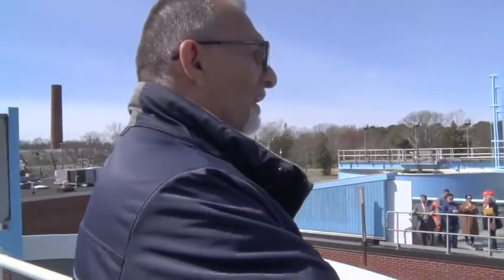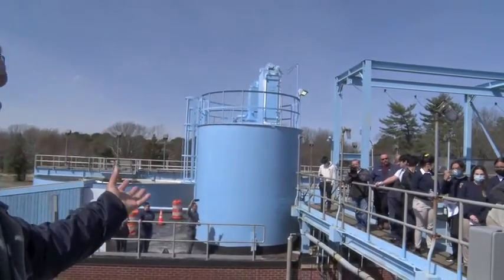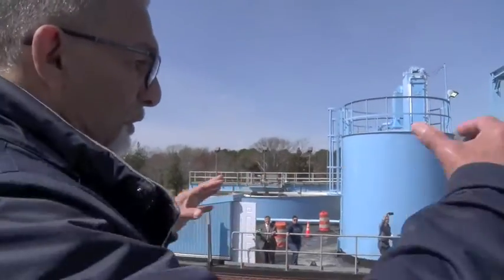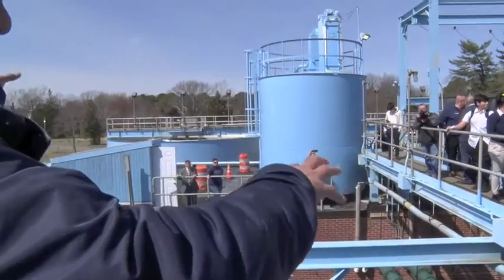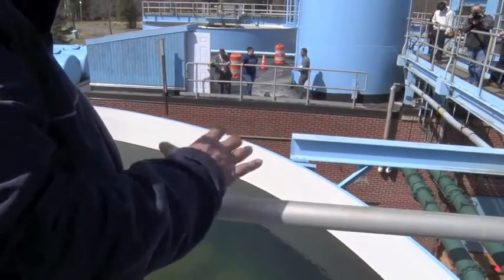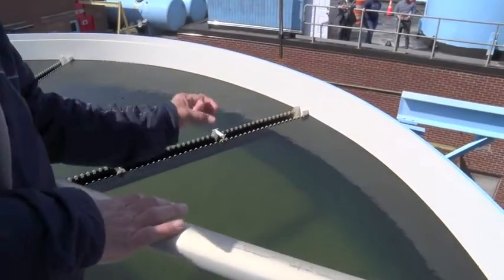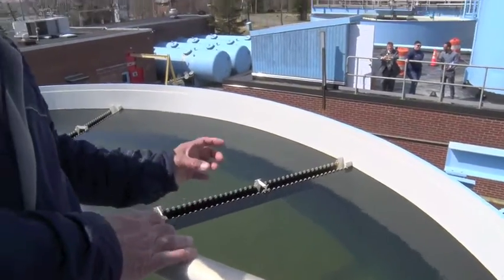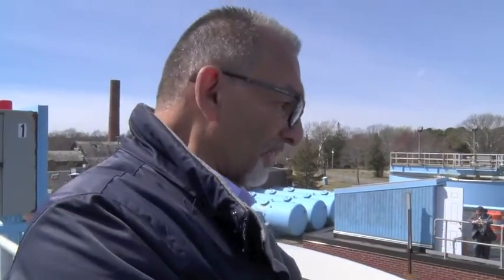These are called clarifiers. When the water comes from the ground to the aerators, we remove the hydrogen sulfide. From there, the water is split into these 2 clarifiers. We have different wells, different clarifiers. Over here, we add the chemicals. We add the coagulant. If you look inside the tank, you see small particles. What the coagulant does is take those small particles and get them together so they get heavier, and then they sink to the bottom. Those particles are iron. That's the iron in the water, and that's what we have to remove from the water.